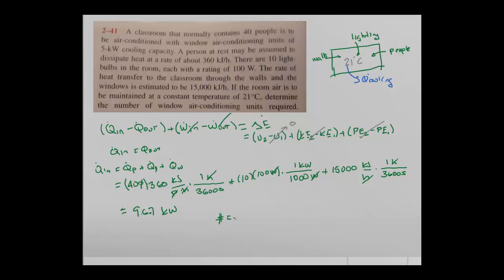The number of units will be Q_in divided by the cooling capacity that each unit has. That is 9.67 kW divided by 5 kW per unit, which gives us more than 1.9. We cannot buy fractional units, so we will need 2 units.